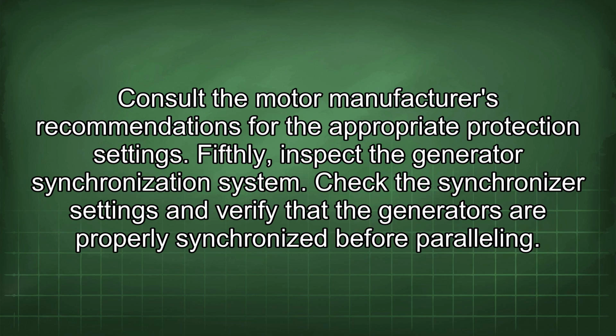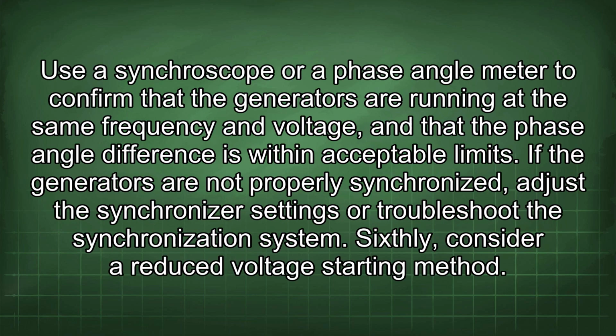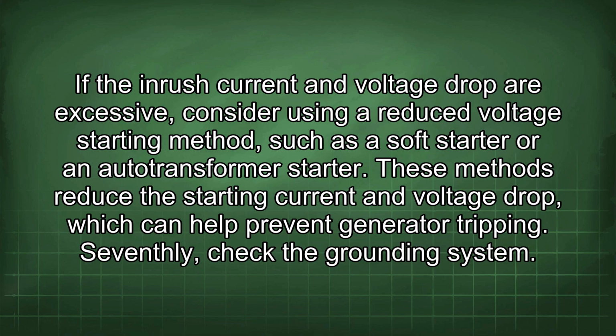Fifthly, inspect the generator synchronization system. Check the synchronizer settings and verify that the generators are properly synchronized before paralleling. Use a synchroscope or a phase angle meter to confirm that the generators are running at the same frequency and voltage, and that the phase angle difference is within acceptable limits. If the generators are not properly synchronized, adjust the synchronizer settings or troubleshoot the synchronization system. Sixthly, consider a reduced voltage starting method. If the inrush current and voltage drop are excessive, consider using a reduced voltage starting method, such as a soft starter or an auto transformer starter. These methods reduce the starting current and voltage drop, which can help prevent generator tripping.